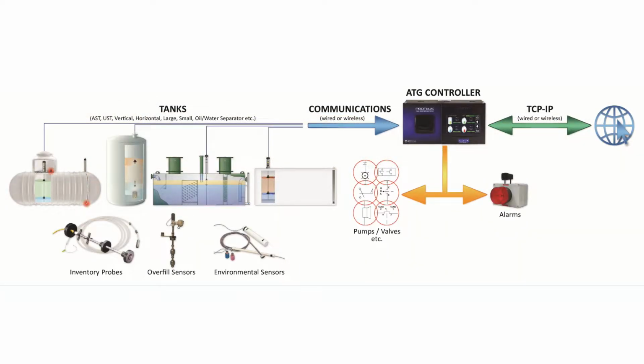Prior to mounting, it is recommended to review the location of the controller, remote annunciators, and remote displays, as well as sensors, probes, pumps or valves, and Ethernet communications to determine the conduit paths needed to meet up with the appropriate knockout. Review the National Electrical Code and federal, state, and local codes applicable to this installation to ensure compliance.